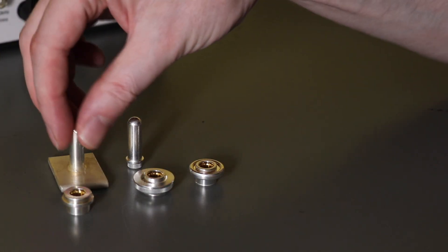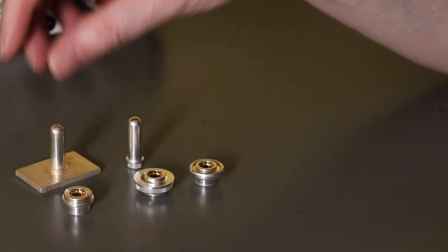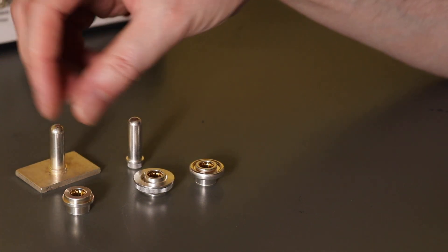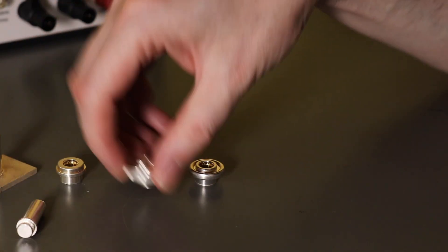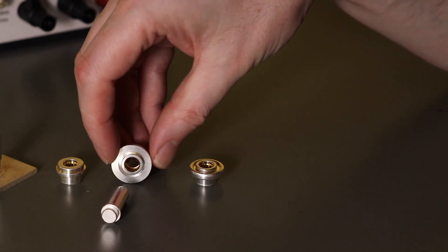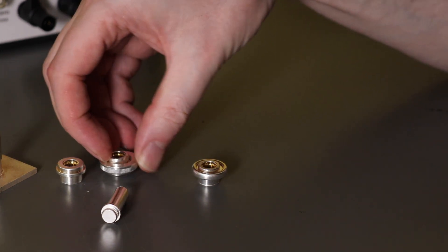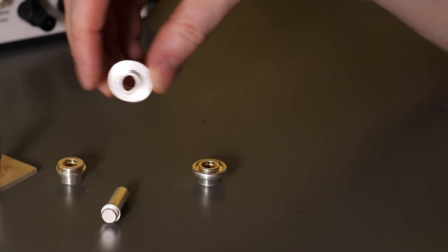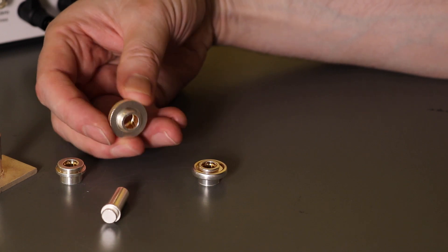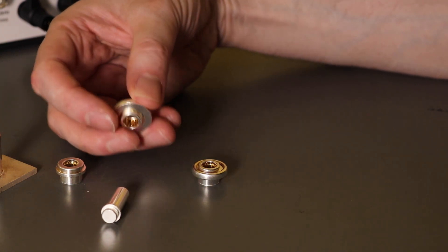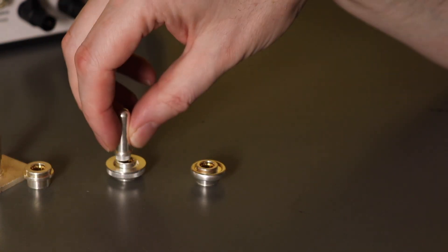The contacts although they are 200 amp rated, it's quite durable really, they've got a 200 cycle mating limitation on them. So what I was going to do and get hold of a linear actuator and set this up with one of the males, one of the females, and then carry out mating cycle and measure the resistance every mating cycle as it's going up and see if there is any appreciable increase in resistance. They also have a spec for the mating force, so if I could find a sensor to measure that as well I will be able to include that and see if the mating force decreases as the number of mating cycles increase, and that's what I would plan to do with these at this moment in time.